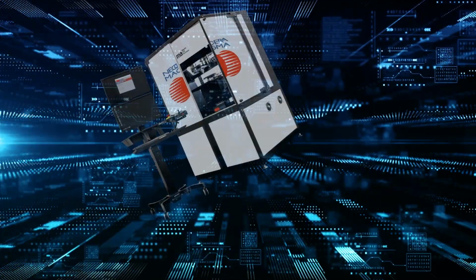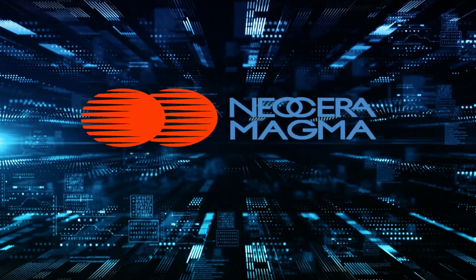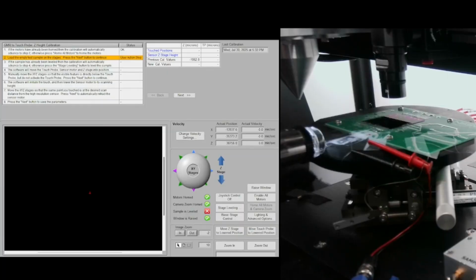We're now performing calibration number 7, which is the GMR to touch probe Z-height calibration. We begin at step 2, since all motors were already homed in step 1. Before continuing, make sure the sample is properly aligned. If needed, you can adjust the rotation using the camera. Step 2 requires loading the sample. Since the sample is already loaded, we'll proceed by clicking Next.